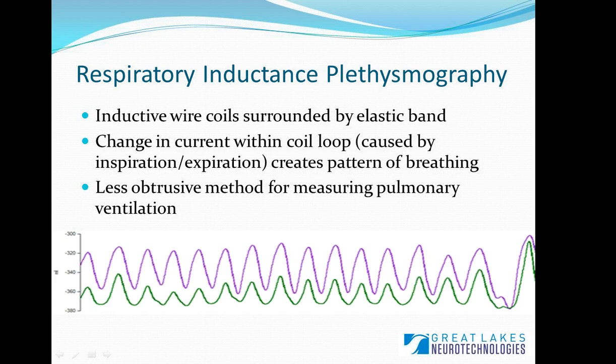The type of respiratory measure I'm going to focus on today is called respiratory inductance plethysmography, or RIP. RIP is a type of respiratory effort band worn completely around the body at the thorax and abdomen. There's an elastic band with inductive wire coils within it. A current is delivered to those coils, and as the current within those loops changes — caused by inspiration, expiration, and movement of the chest and abdomen — this creates a pattern of breathing, producing the standard sinusoidal waveform you might see in a healthy subject.